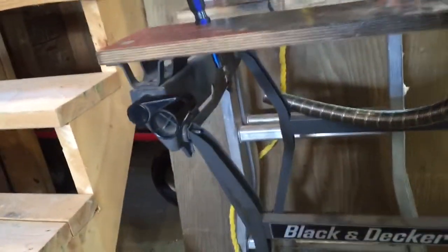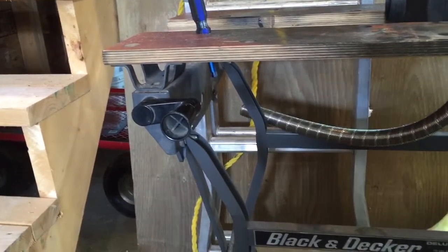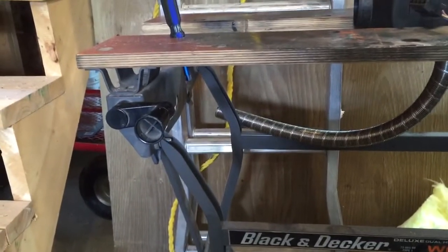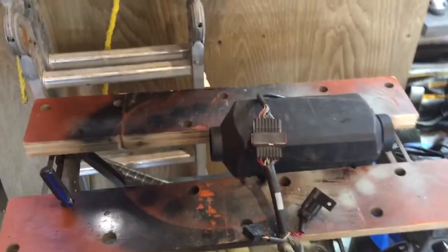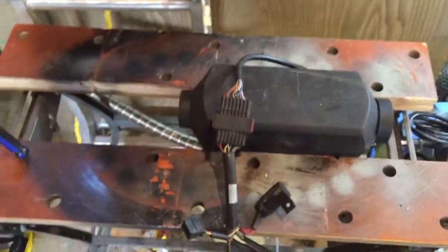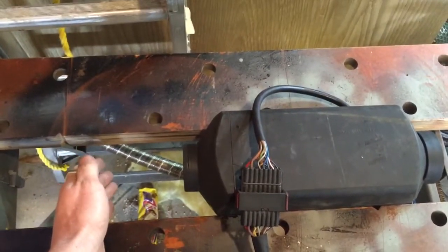There's the exhaust - very clean, no black exhaust. When she shuts off she'll emit a little bit of white exhaust, then she shuts down. That's about it. She's starting to cool off right now. She's starting to tell the system to slow down and consume less fuel.